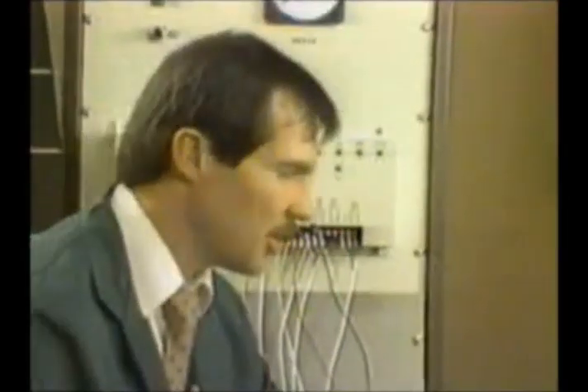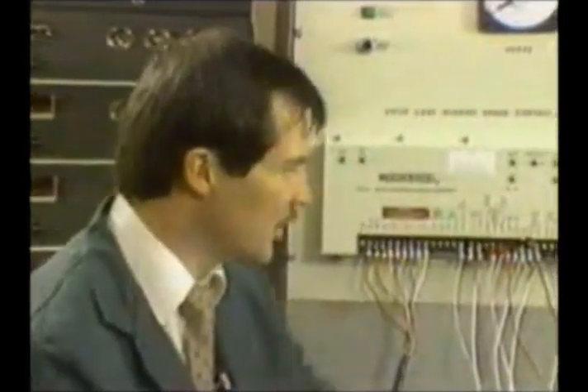I want to point out, once we get started, the start fuel limit circuitry is overridden. I'm going to go ahead and start up at idle speed here. I hit it. You can hear the engine's trying to crank over. We're calling for voltage and it just isn't getting enough fuel. So in this case, 30% wasn't enough. It just wasn't enough fuel to start this prime mover.